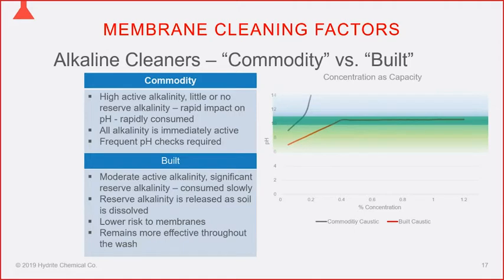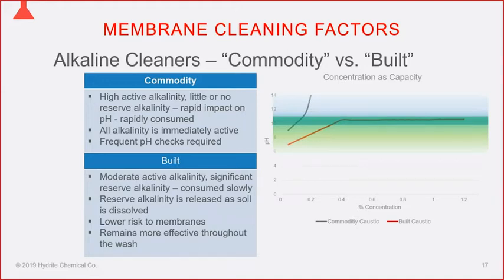With built products, you can add a lot more chemical to solution before exceeding pH 11. They have a lot more alkalinity — soil-absorbing capacity — without exceeding the upper pH limit. Once you hit your pH target using a built product, its buffering capacity means the pH won't drop much during mid-wash; it maintains the desired pH and cleaning capacity throughout the entire cleaning process. The operator doesn't have to check as often and can be assured the cleaning chemistry will carry through to the end of the wash.